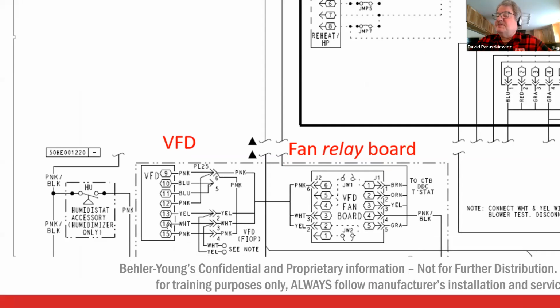So again, I can simply check that. If we're calling for low speed, pink goes through, relay energizes, sends it back out in the yellow, and that energizes terminal 13. It turns on low speed. I don't know how much easier that is. I can check from pink to yellow, pink to white to see if I should have the blower on. And if not, then the problem's at the drive. If I'm not calling here, if pink to white and pink to yellow are open, then that obviously means we're not calling for anything.